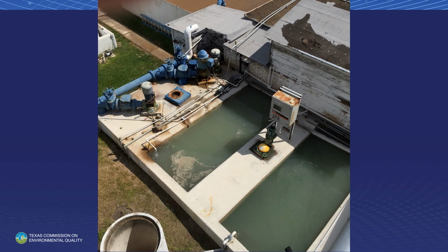Next example is an example of a flash mix that sometimes don't flash so well. That's primarily because they couldn't afford to replace the motors and impellers and stuff in that flash mix to actually do any stirring. And sometimes you run into that situation at a water plant. Obviously, having a replacement spare part on the shelf was not these guys' intent at all. So occasionally you have problems that you run into that look like this.